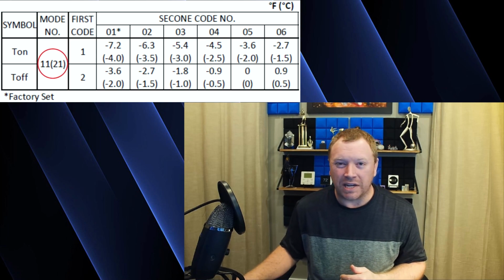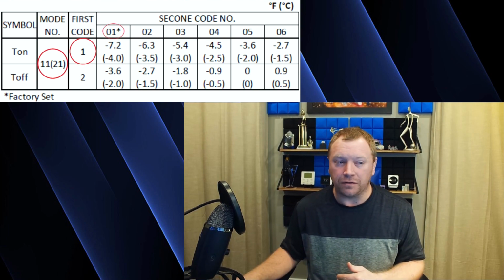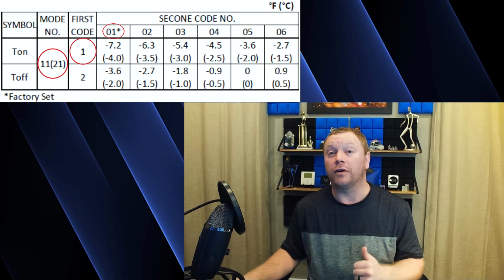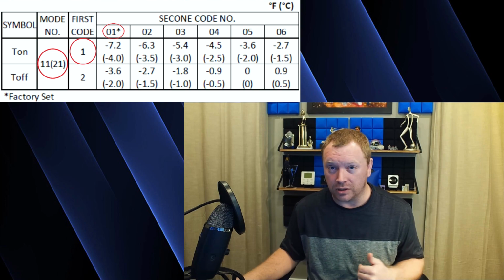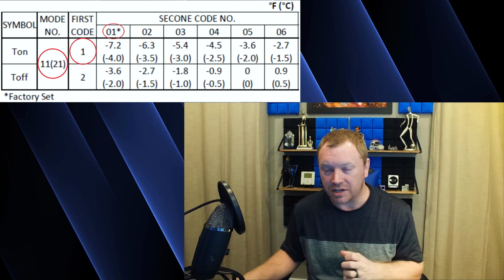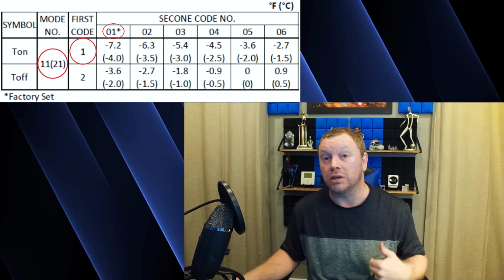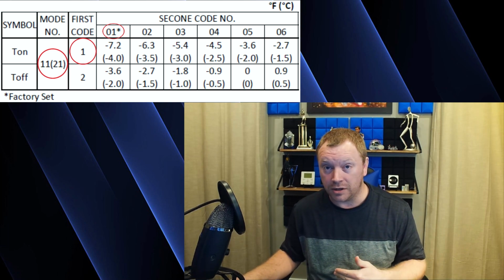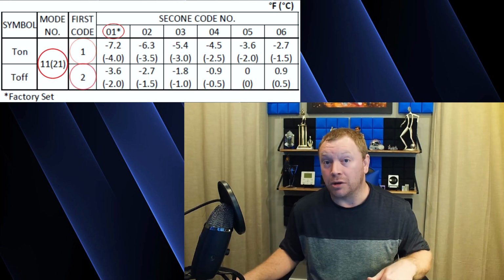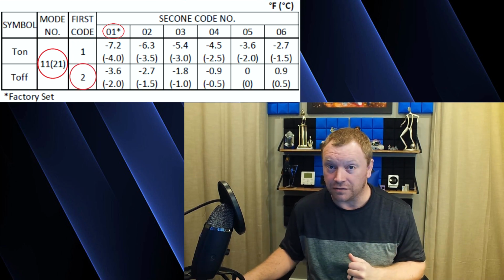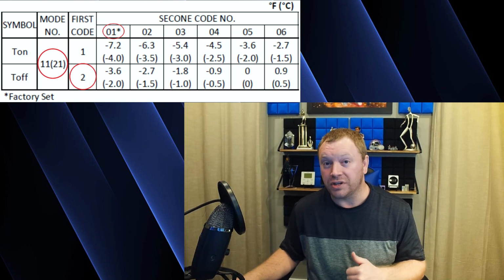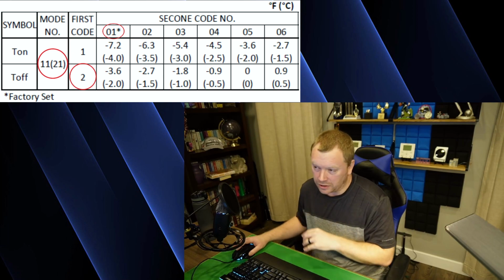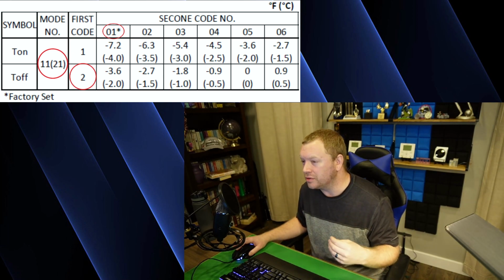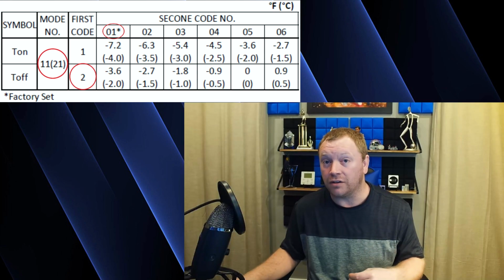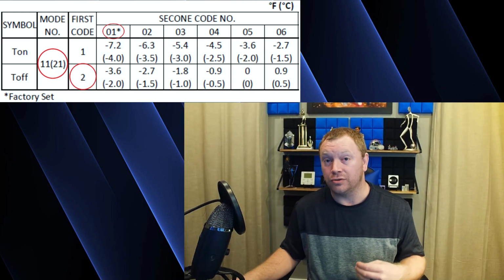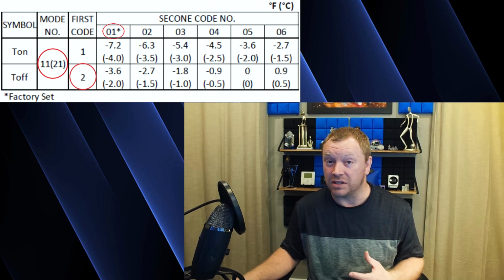So your T on temperature, your strip heat on temperature, number of degrees below set point is going to be mode 21. Setting number 1-01 is the default, which is a 7.2 degree Fahrenheit drop or droop below the set point. So if your set point is hypothetically 70 degrees, it would drop 7.2 degrees below that before the strip heater kicks on. And then mode 21, setting number 2-01, which is the default, is going to be 3.6 degrees. When you read it on the chart, I'll put a picture of it up here. You'll see that it says -7.2 and -3.6 for your T on and your T off. For mode 21, settings 1 and 2 respectively, if you are going to leave them at the default setting.